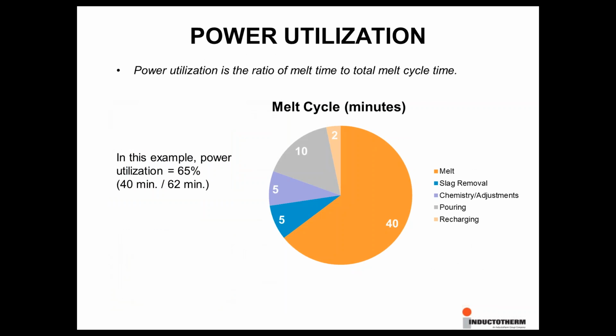Another factor discussed is power supply utilization. Power supply utilization is a ratio of melt time to the overall total melt cycle time. The total melt cycle time is made up of the melt time as well as time required for tasks such as temperature measurements, slag removal, chemistry analysis, pouring, and initial charging of the furnace. We sometimes refer to this as the off time or hold time portion of the melt cycle. In this specific example, the melt time is 40 minutes. The time required for off time functions is 22. Utilization is 65%.